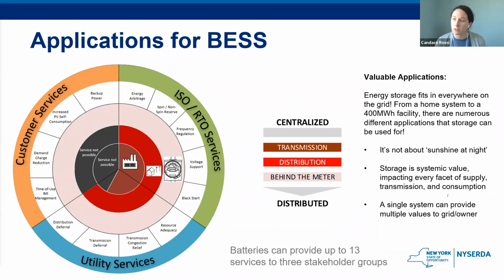This is similar to the energy arbitrage. It's basically using storage to buy when the energy is cheap and utilizing it when the energy is more expensive. The demand charge reduction is a little similar as well, but it helps reduce a building's peak demand charge by shifting consumption times. Next, we have increased PV or solar self-consumption, which means minimizing export of energy generated by solar systems to maximize the financial benefit of the solar.